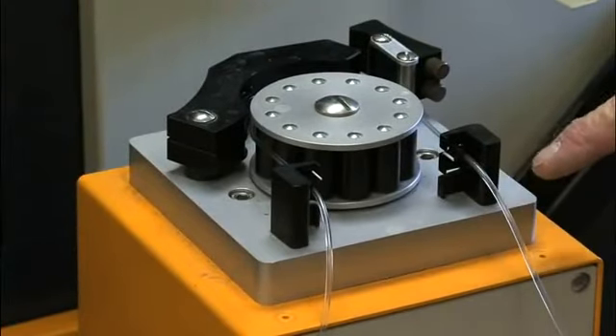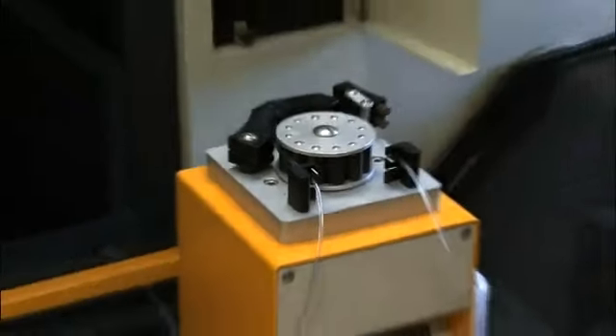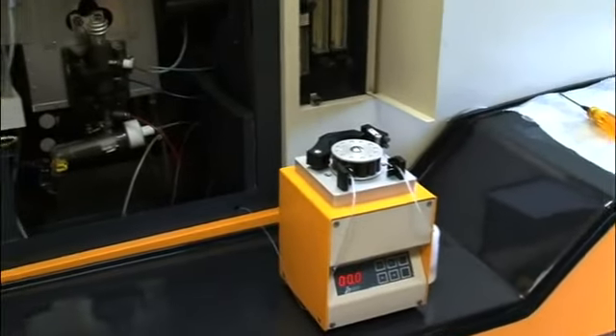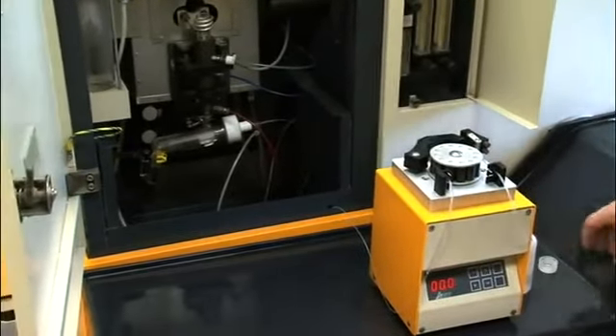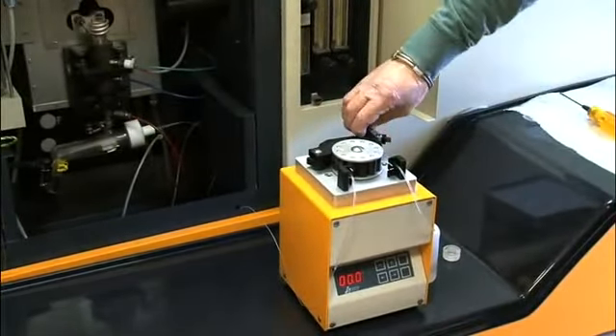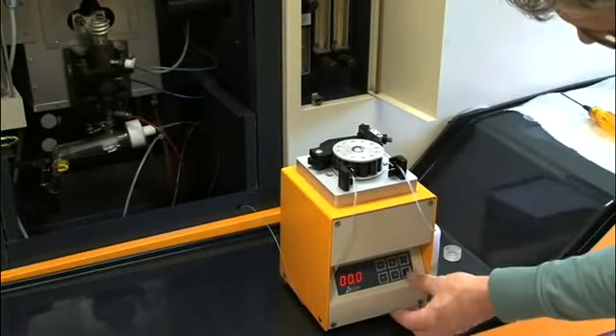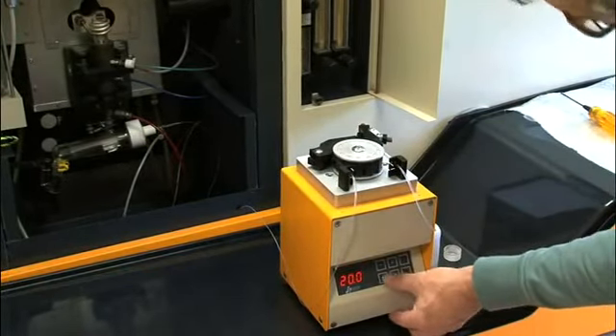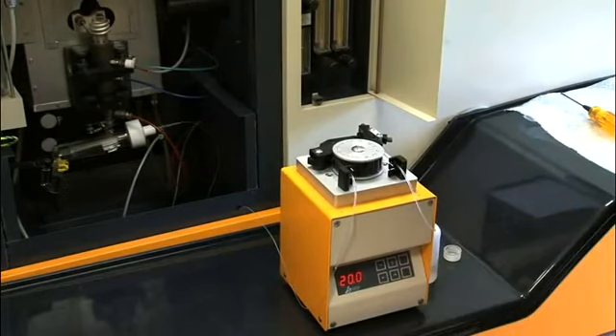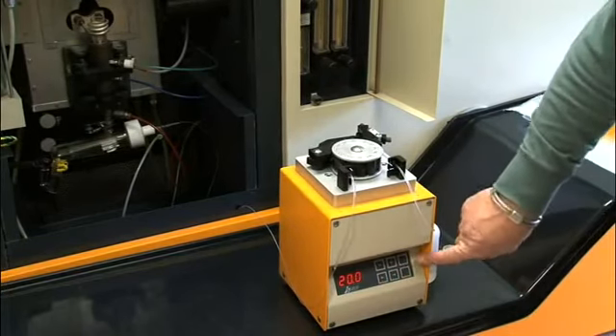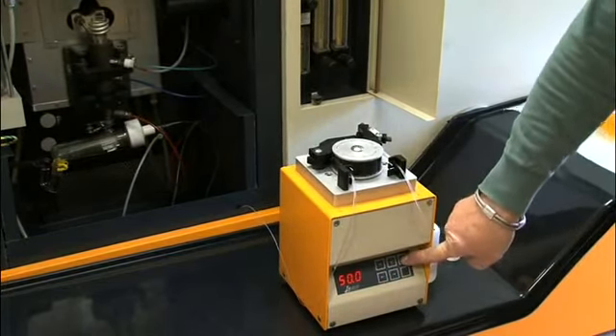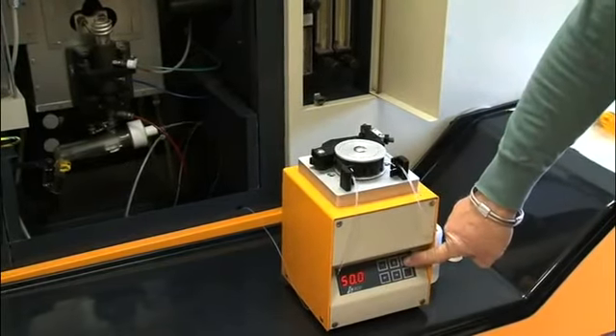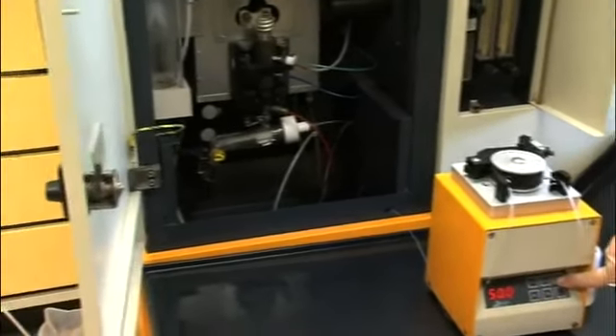So, yeah, even without the pump, that nebulizer will have Venturi effect on the very tip, so it'll just draw it in on its own. But we use this so that it's got a steady flow. Wrong way. If you want to speed it up, you just keep your finger on that, and then you'll see a mist in the spray chamber now. All right, so put this back on.